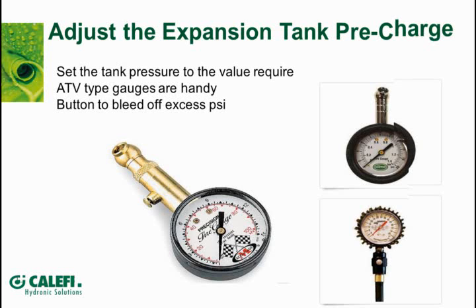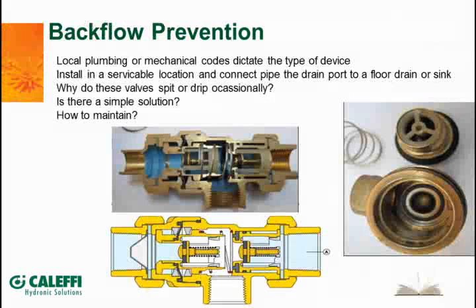And that's really important on the solar tanks, the Caleffi solar tank that I showed you earlier. Those come, for some reason, with about 45 or 50 pounds pressure in them, so you certainly don't want to put that on a system and only fill it to 20 pounds pressure, 30 pounds pressure, because you're not going to have much expansion room if you've got your air charge in your tank that much higher than the fill pressure. So I want to talk about another device, the backflow prevention.